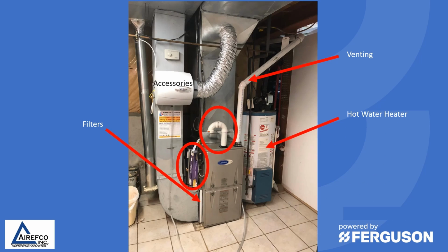We also note that there's a hot water heater sitting next to the gas furnace. This hot water heater is also a gas appliance and it needs air for combustion. So is there sufficient air in this space to operate the furnace and the gas hot water heater? Looking at this pipe coming down, it looks like it's a makeup air vent, which is good, as we're drawing the air for the furnace from the space, and we also have a hot water heater. So we want to make sure that we have enough combustion air to support combustion in both the gas furnace and the hot water heater.